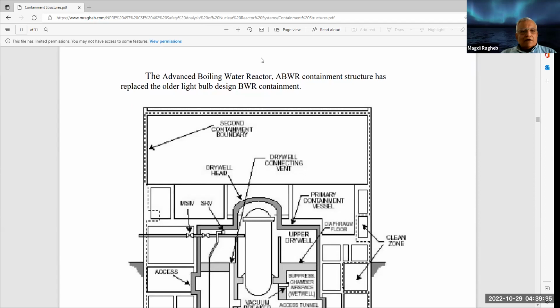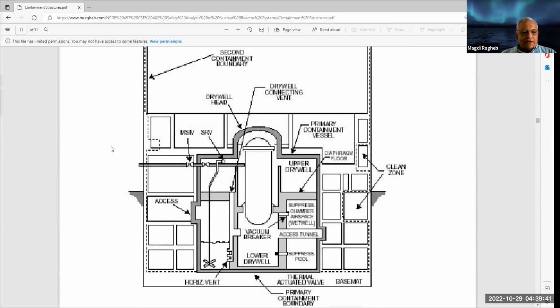So this is the advanced boiling water reactor that the General Electric company tries to build today. You notice here that you have the pressure vessel right here. I lost my mouse here apparently. Oh, here is the pressure vessel. And the pressure suppression pool is a toroidal shape here around the bottom of the reactor, where, say, a safety relief valve, SRV, here would relieve the pressure if it increases beyond the design pressure and quench it in the water in the pool.